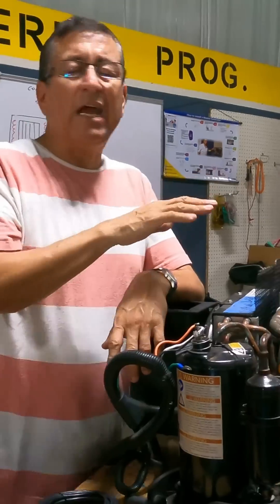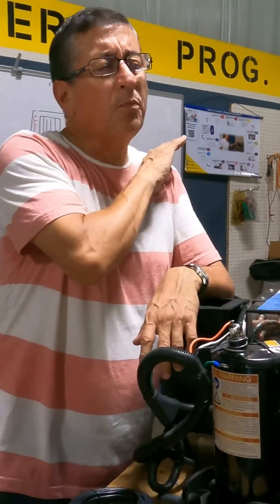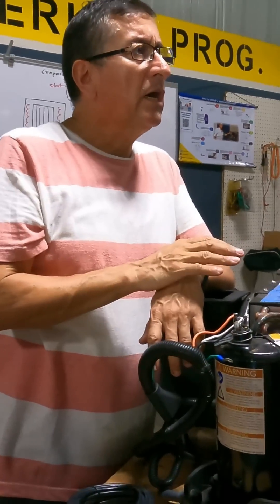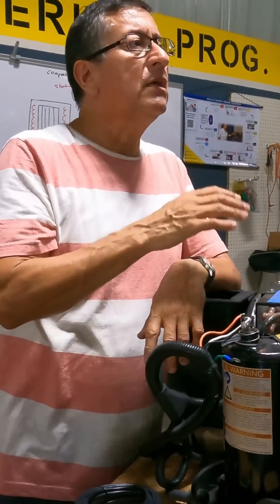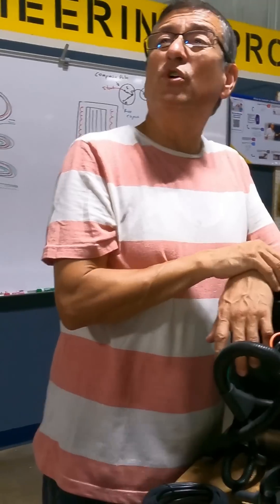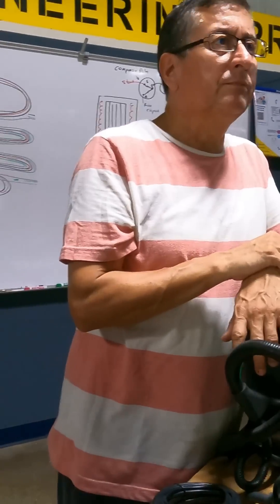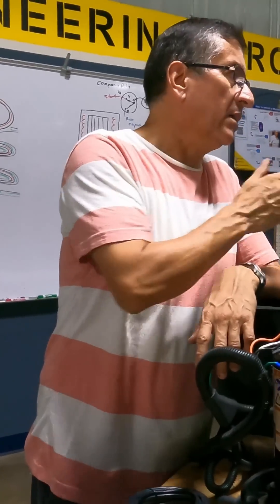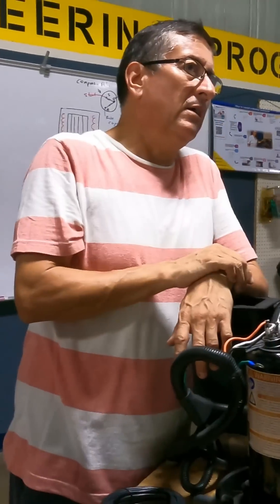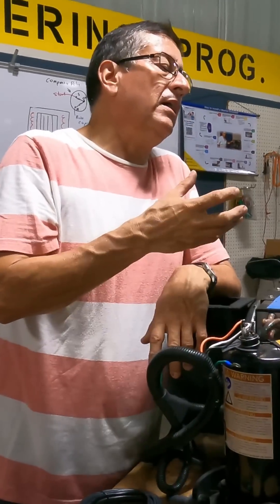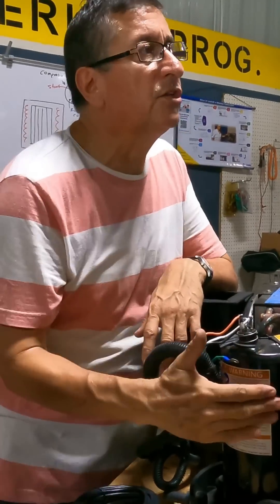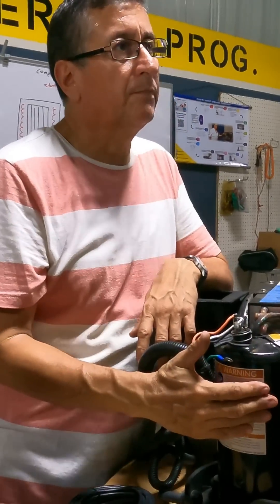When he added the refrigerant, the compressor worked perfectly for two weeks. And then yesterday, once again, the compressor would not start. The problem? There was a leak — he never fixed the leak. He just added refrigerant, the refrigerant leaked out again, humidity entered the system, and destroyed the compressor. Compressor gone.